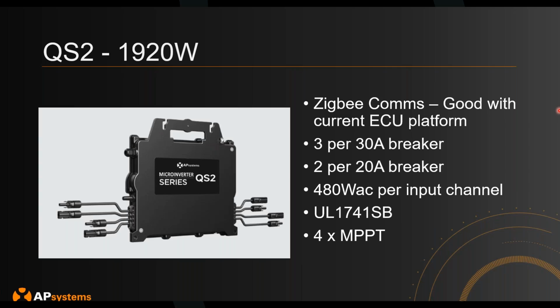The QS2's AC output power is 1920 watts, which allows you to put exactly 3 of these on a 30 amp breaker, or 2 of them on a 20 amp breaker. This also means you can do 480 watts AC per input channel. So what kind of panels would you put on these? I'd probably put 500 watt panels, which gives you a little bit of clipping. You can go higher, and I think 550 watts would be the panel wattage if you want a 1.2 clipping ratio.